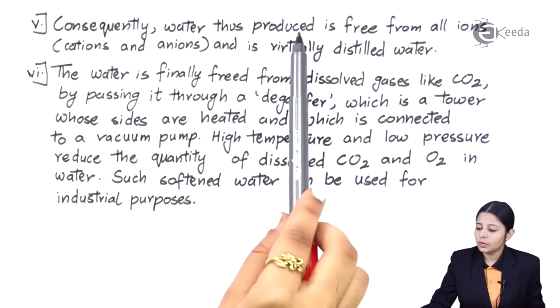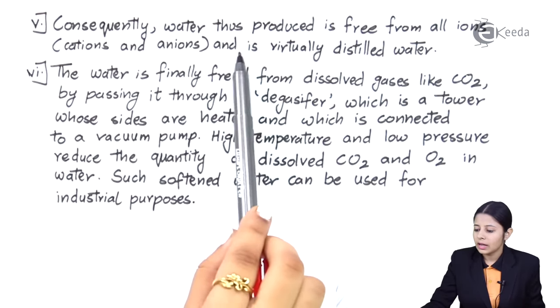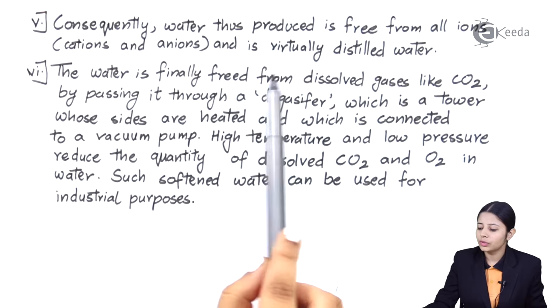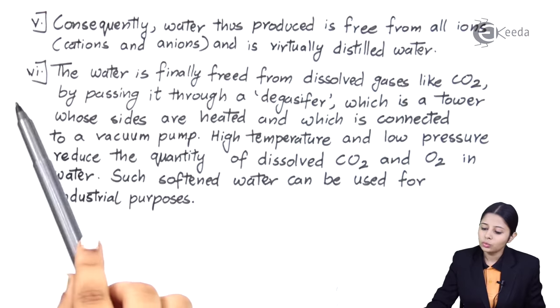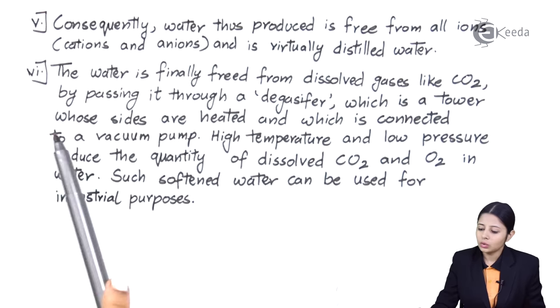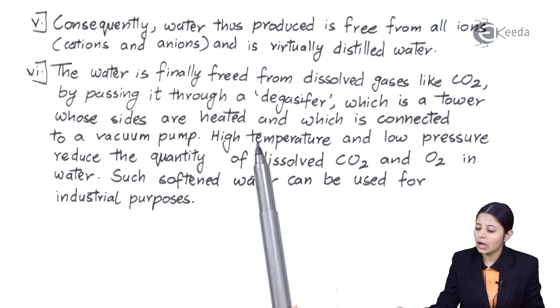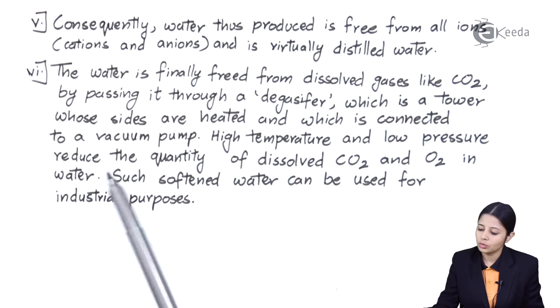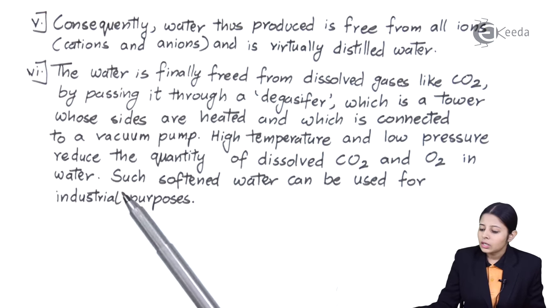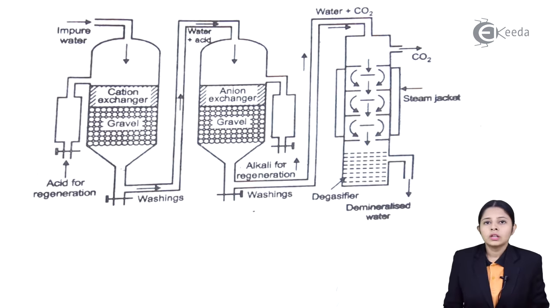Consequently, the water produced is free from all ions — cations and anions — and is virtually distilled water. The water is finally freed from dissolved gases like CO₂ by passing it through a de-gasifier, which is a tower whose sides are heated and which is connected to a vacuum pump. High temperature and low pressure reduce the quantity of dissolved CO₂ and O₂ in water. Such softened water can be used for industrial purposes.